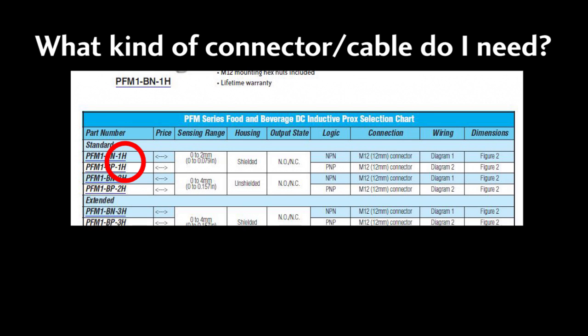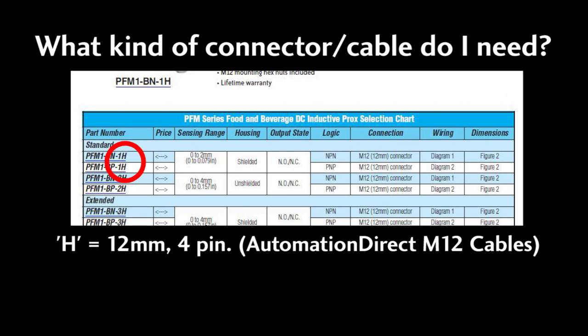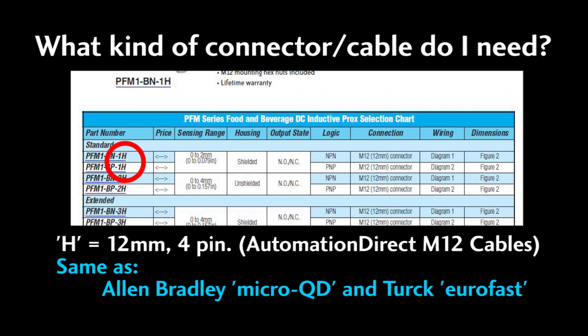The best way to tell what kind of connector a sensor uses is to look at the last character of the part number. An H is a 12 mm 4 pin connector that all of the AutomationDirect M12 cables are compatible with. This is the same connector as Allen Bradley's Micro QD and Turck's Eurofast.